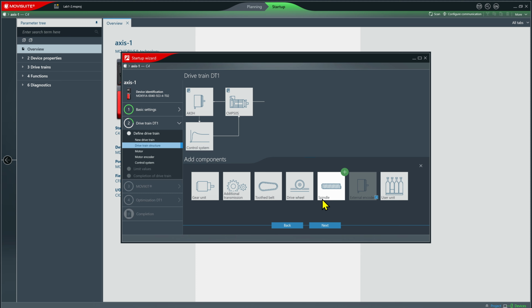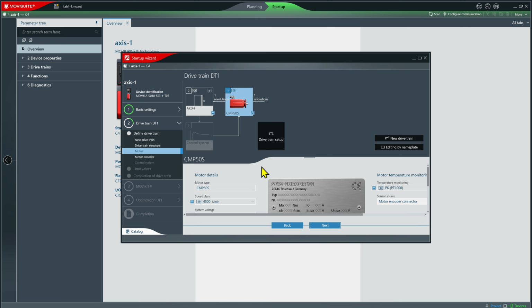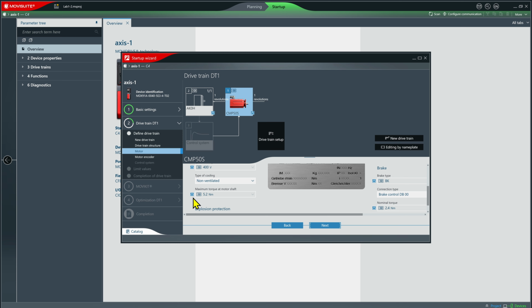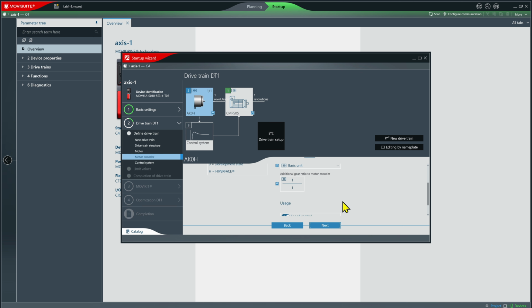And there's my drivetrain with everything set up. I click Next again. It gives me a chance to review my motor details. Notice a lot of things are locked out. That's because it's relying on the settings in the electronic nameplate. So it's only letting me change a few things. For example, I could alter how the sensor's wired up to the VFD, but of course I won't because this is correct. So I click Next again.